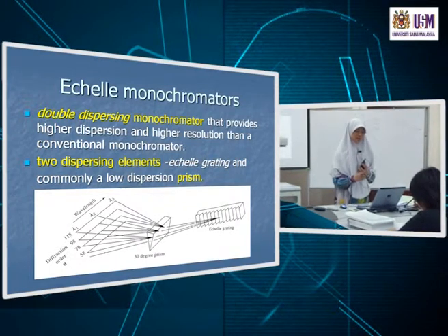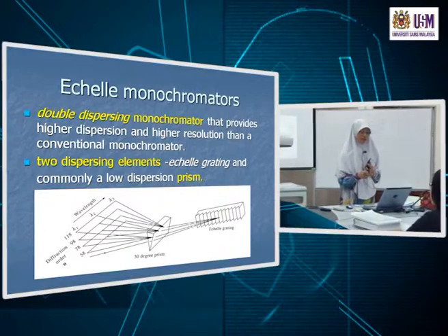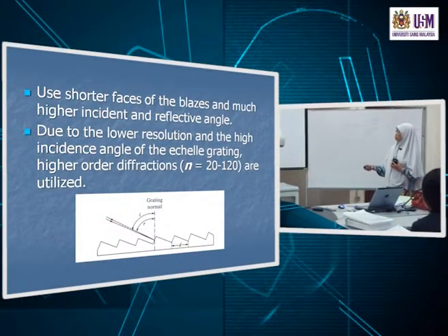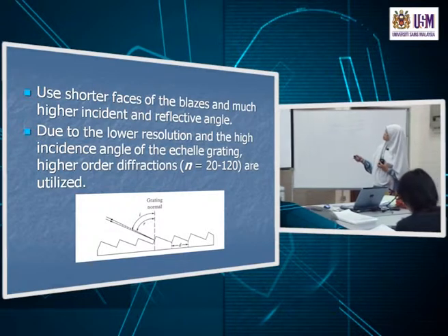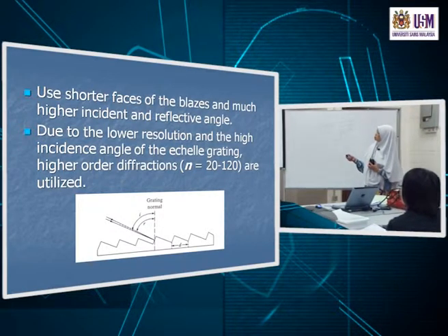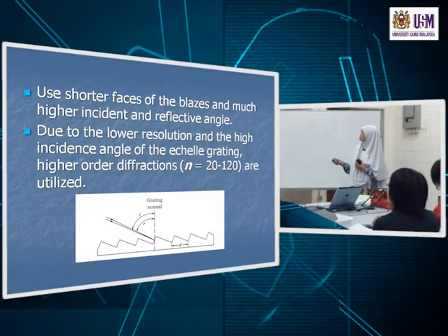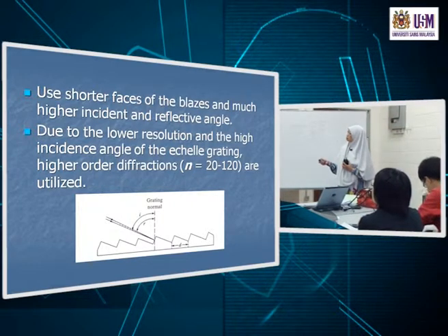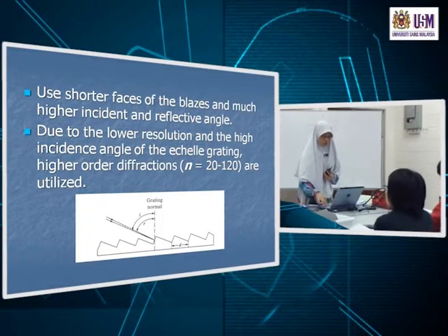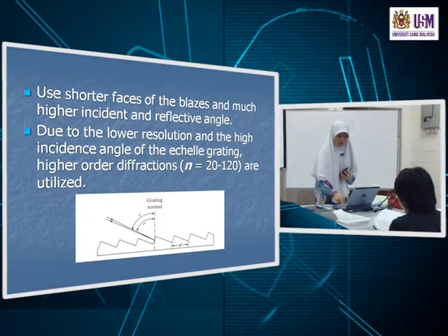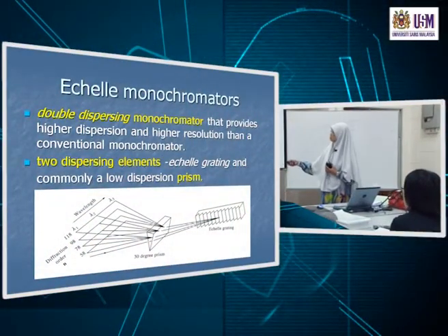So we have two dispersing elements, the Echelle grating plus a prism. And as we have said, the Echelle grating uses the shorter surfaces of the blazes, and you use the higher order diffractions, n equals 20 to 120.